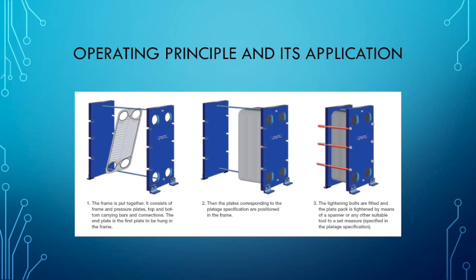Okay, how it works. The gasket plate heat exchanger optimizes heat transfer. The corrugated plates provide easy heat transfer from one gas or liquid to the other. Plates from a gasket plate heat exchanger are fitted with elastomeric gaskets. These seal channels and direct the mediums into alternate channels. The plate pack is between the frame plate and a pressure plate. It is then compressed with bolts between the plates like this.